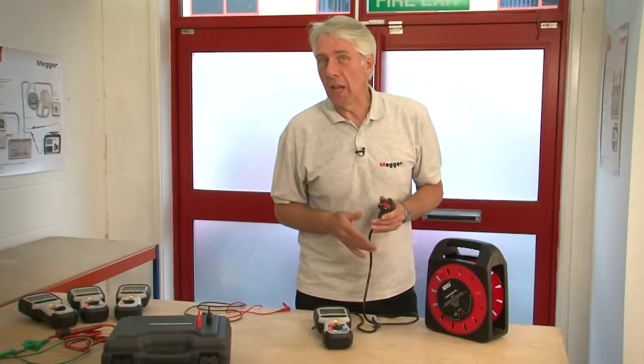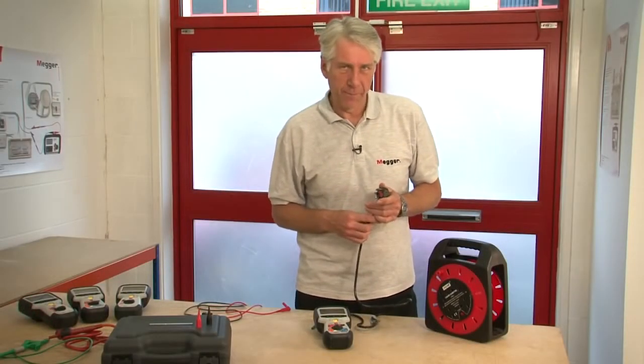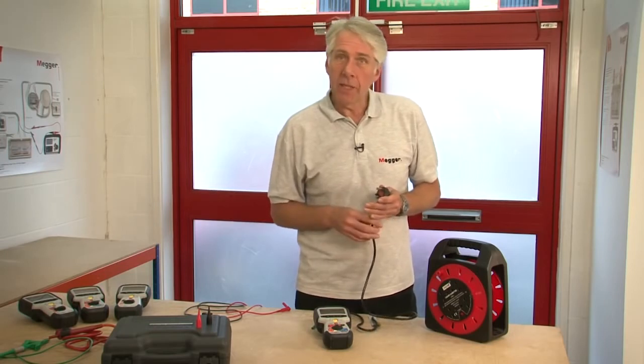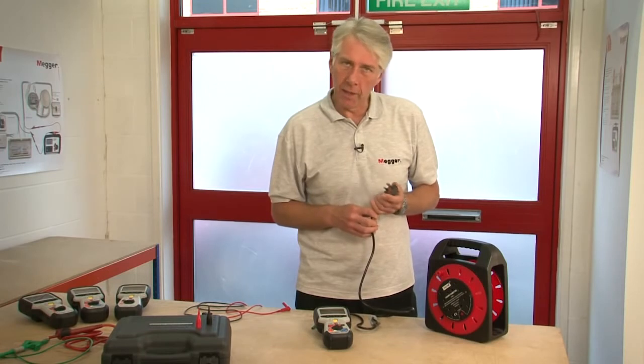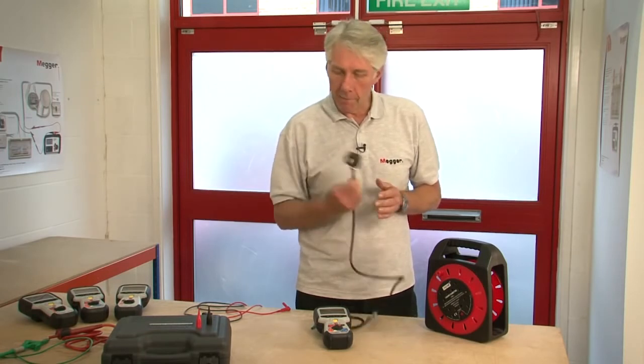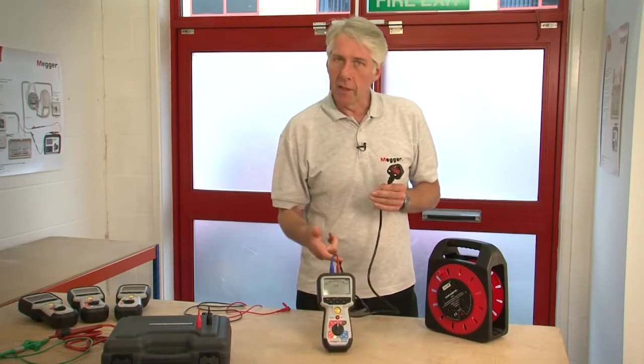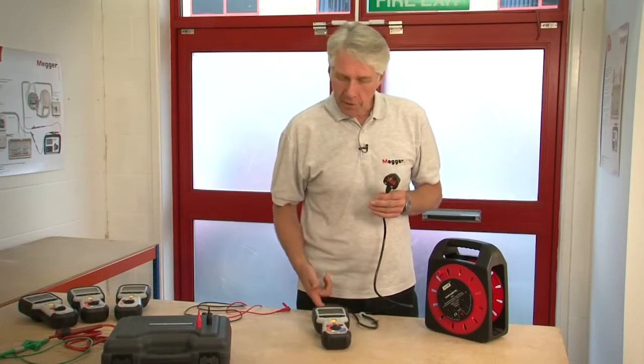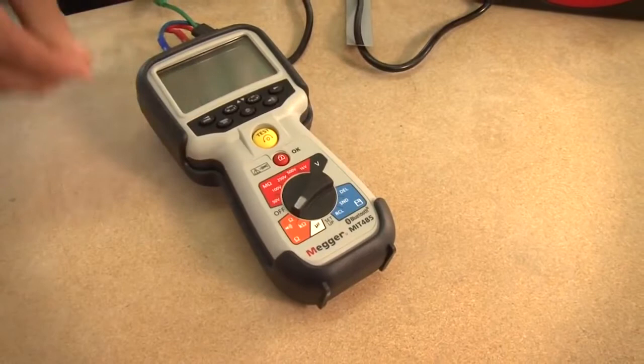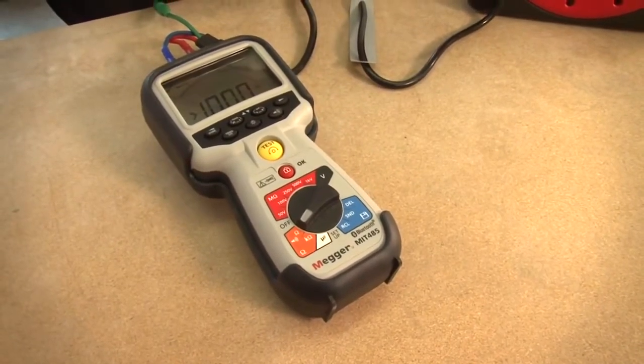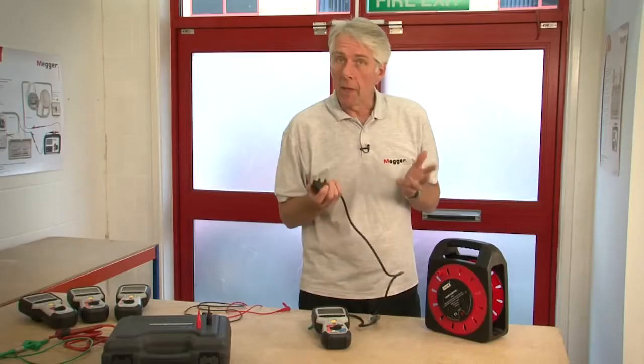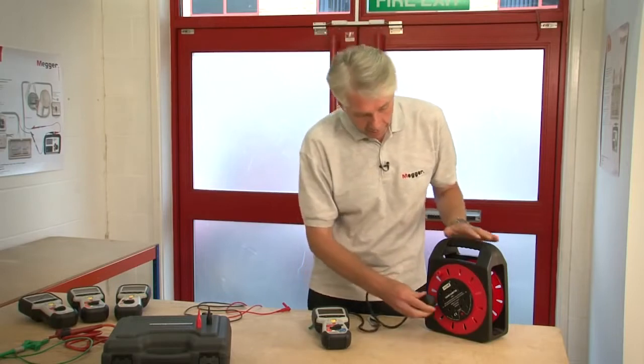We're now going to have a look at the test inhibit function. All of the products in the MIT400 family are protected against accidental connection to a live mains supply, and I'm going to show that to you now. So here I have a mains lead which is connected to the device. Let's switch it to the continuity range. It will read open circuit. I'm now going to simply plug it into the mains.